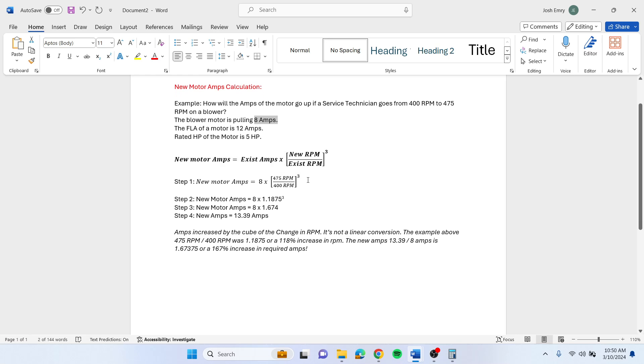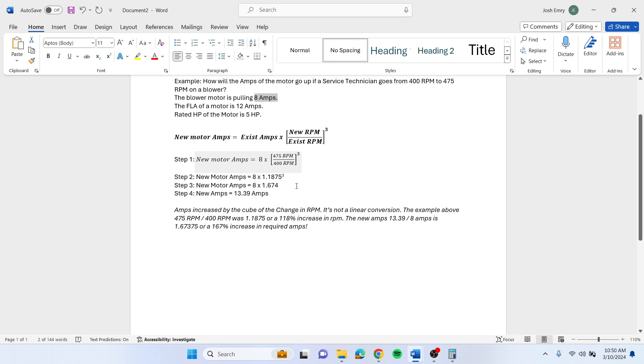So plug that information into the equation that you need. Your existing amp is 8. Your 475 RPM divided by 400 RPM cubed. Step 2 is you take 8 times that 1.1875 cubed.